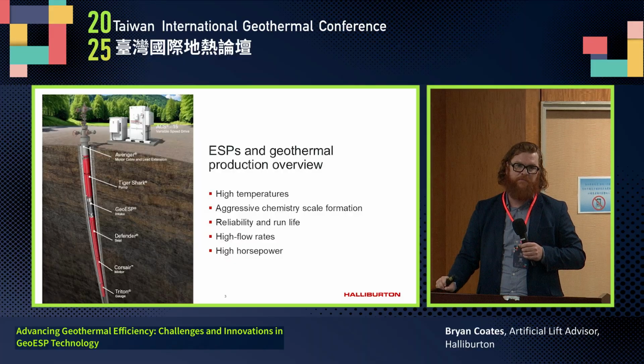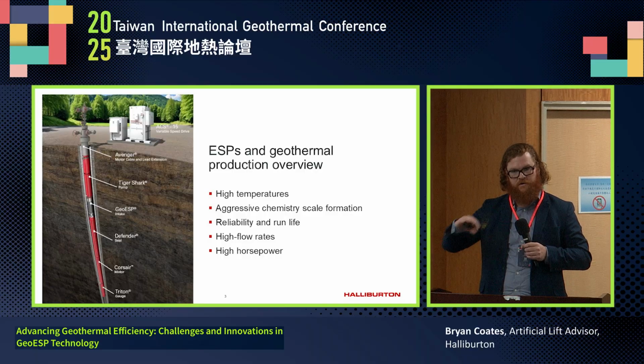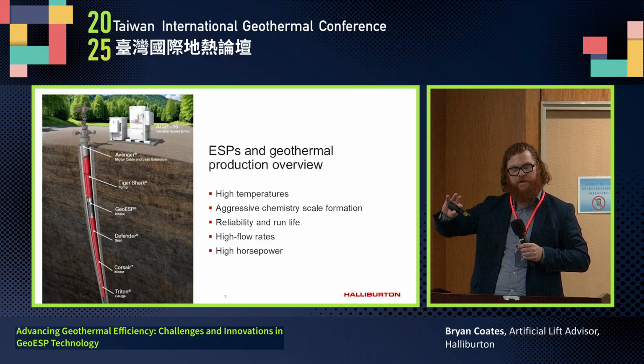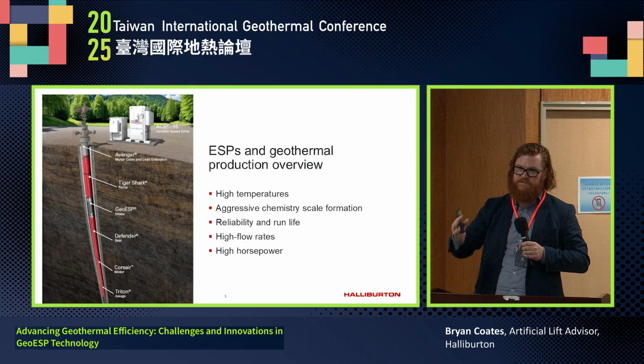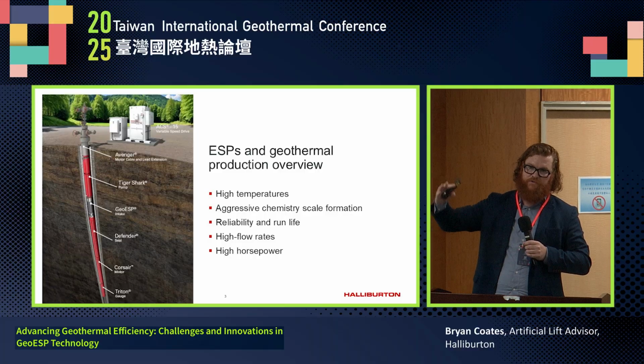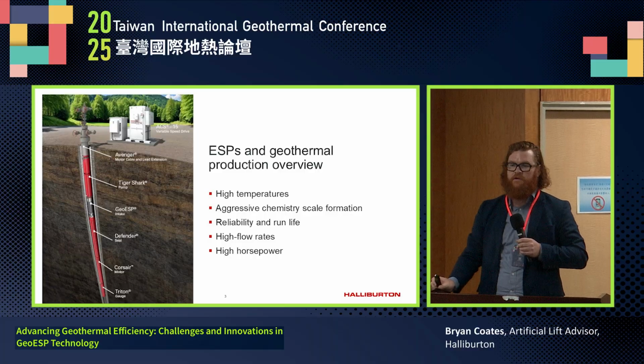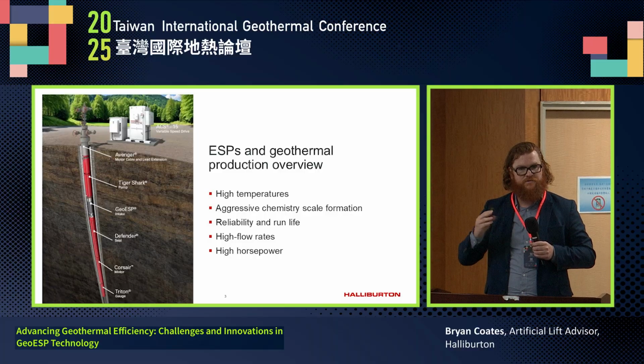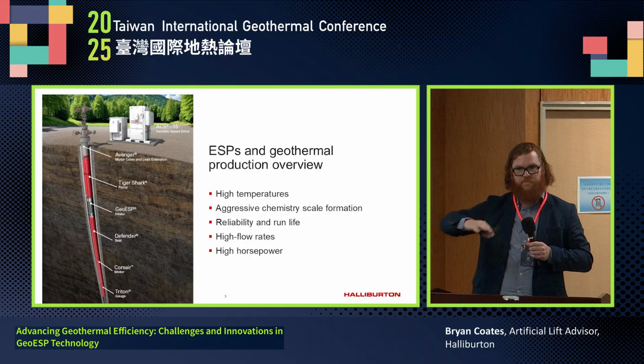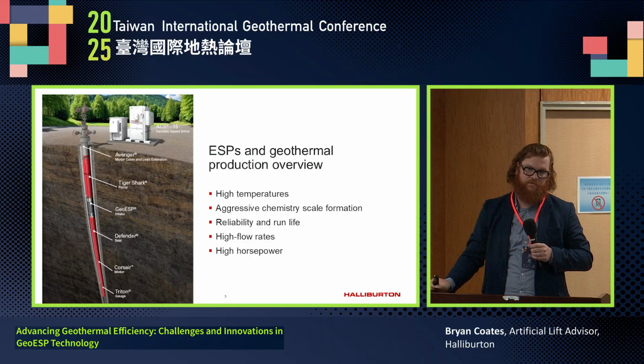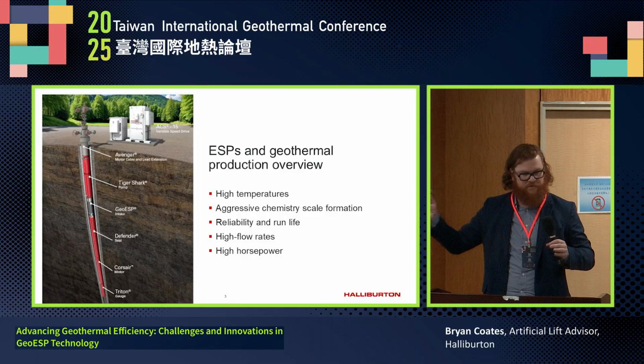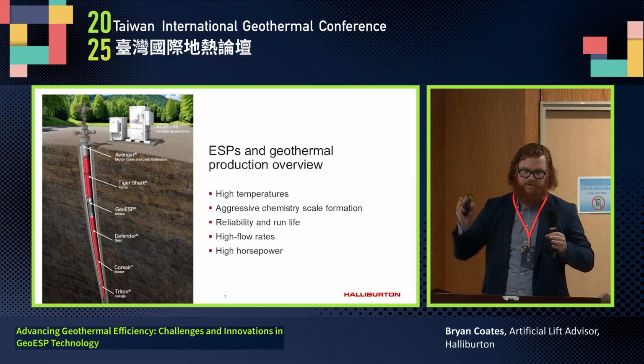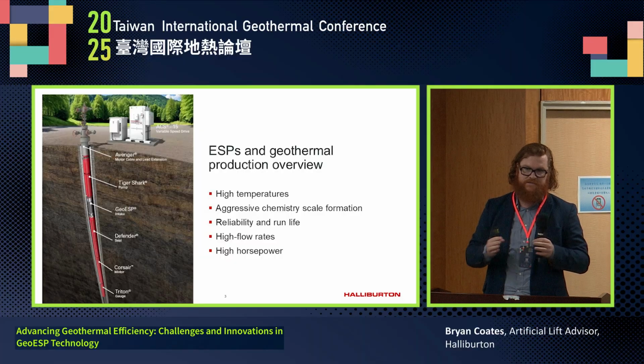And then lastly is the pump. These are multi-stage centrifugal pumps, so you have an impeller and a diffuser. Rotating impeller, stationary diffuser, takes the fluid, puts it into the diffuser, redirects it into the next stage. Every stage is rated for so much head or lift and so much flow. Stack, call it 20 stages together, and it creates the same flow of those 20 stages, just 20 times the lift.